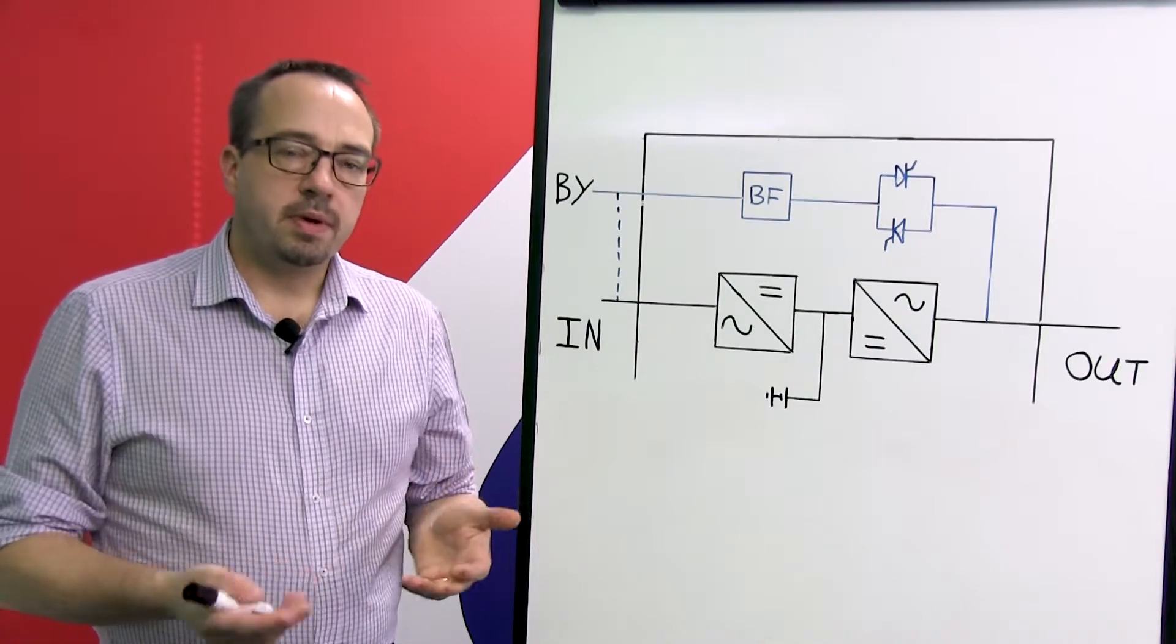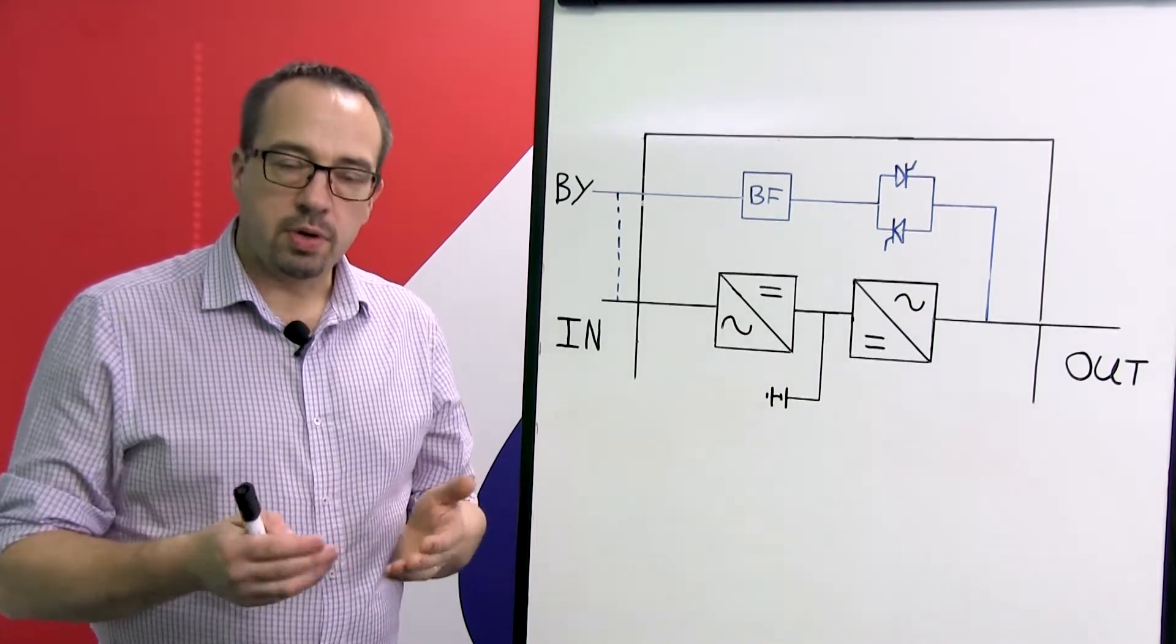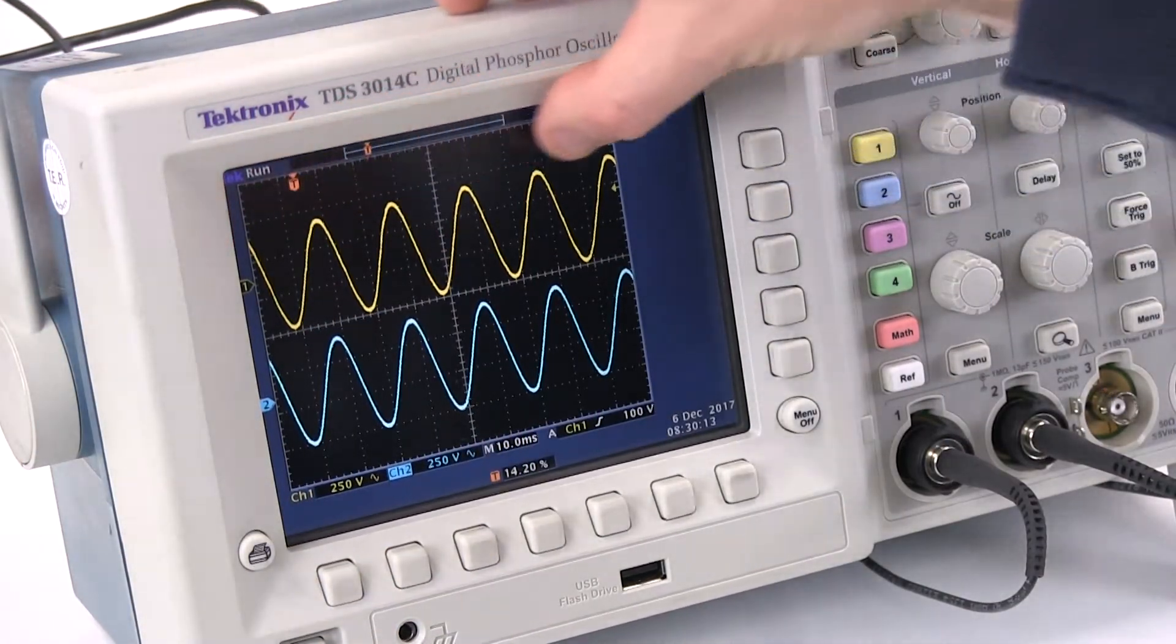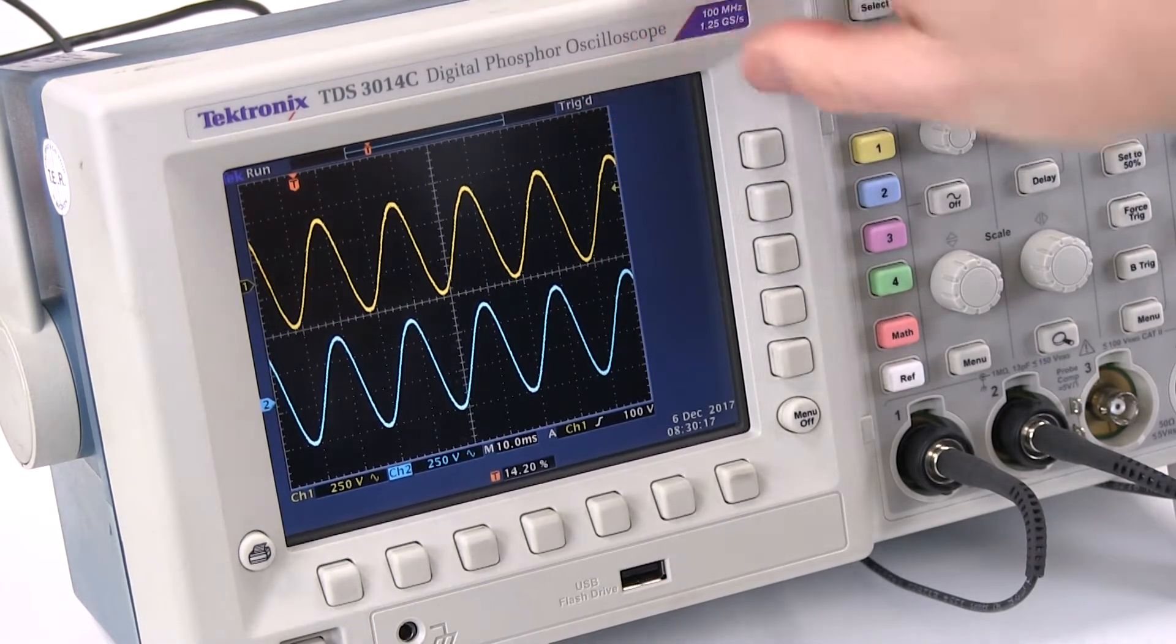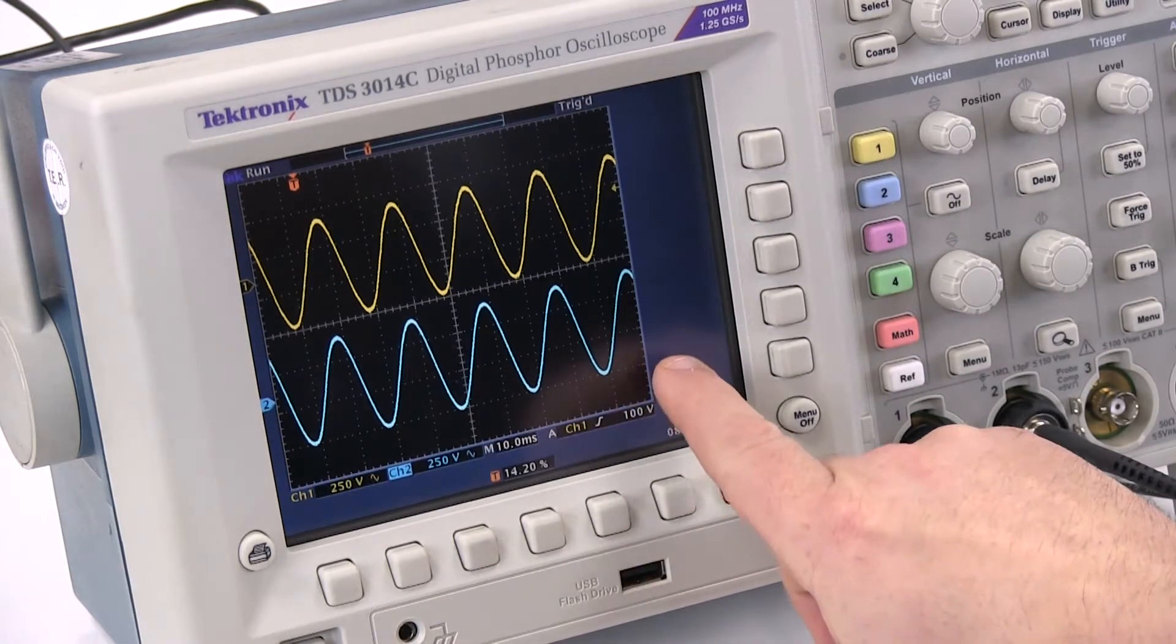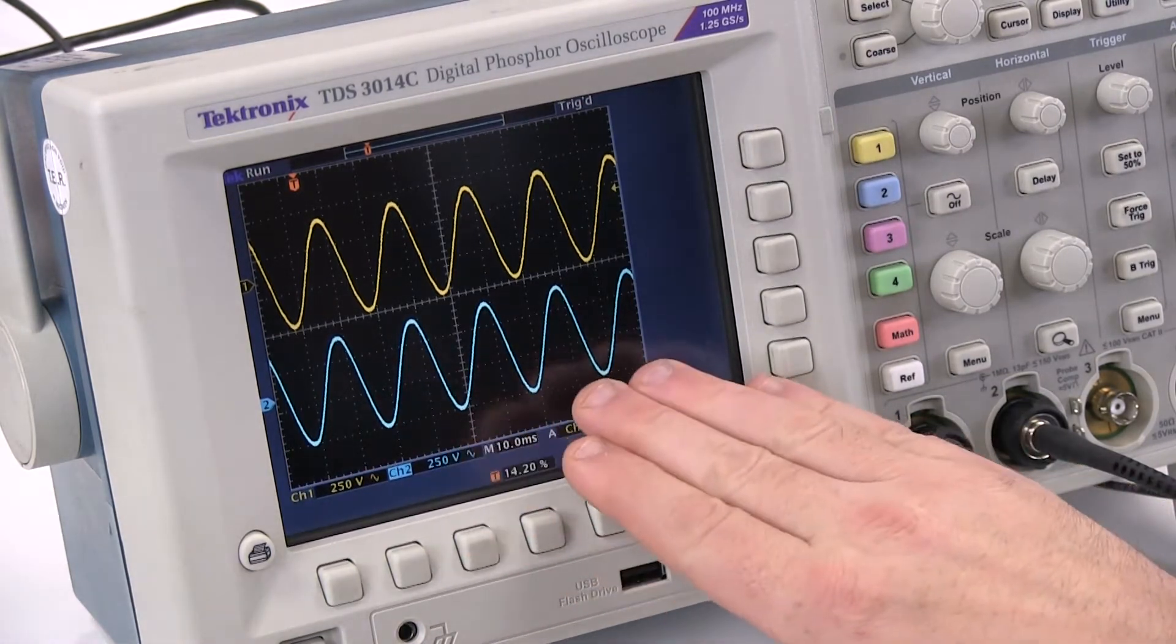Now exactly what do I mean by no break? Well, if we take a look at the oscilloscope I can show you in a little bit more detail. If we take a look at the oscilloscope here, the waveform across the top is effectively the main supply coming into the UPS. The waveform along the bottom is the waveform supplied to the critical load and hence the protected side of the UPS.